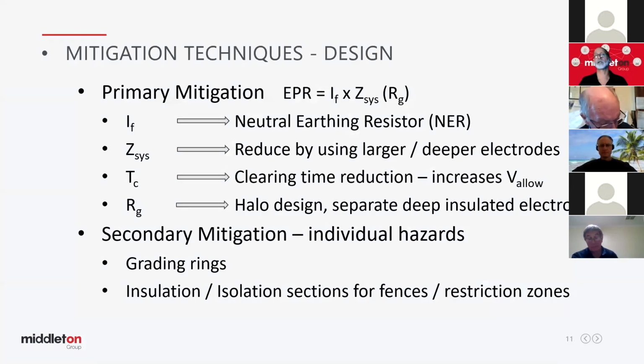When you do your modelling and your calculations, you'll find that the further you push that insulated electrode down into the ground, the more you lower the EPR, the soil voltage at the surface, and therefore lower the touch voltages that you could be exposed to on conductive surfaces on the surface of the ground, if I didn't make that too complicated to listen to. So they're pretty complex designs, pretty hard to nutshell in 30 seconds. Happy for people to phone up and have a discussion afterwards as well. I hope that's answered the question. If it hasn't, reiterate it while I have a sip of water.